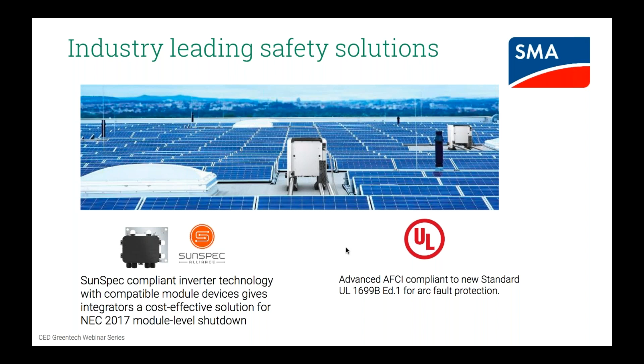The solution we've developed is based on an industry standard that we worked with SunSpec and other participants in the solar industry to develop, a standard for communication between the inverter and the array to implement module level rapid shutdown. And it's really a very simple solution. Essentially, we have integrated into the Core 1 inverter a transmitter that sends out a standardized keep alive signal that is defined by a new SunSpec standard. So anytime the inverter is running, is powered, it will be sending out this signal over the PV lines. That signal's carried over the PV string conductors, so there's no need for additional wires or even wireless communications to carry this signal into the array and to the individual modules in the array.